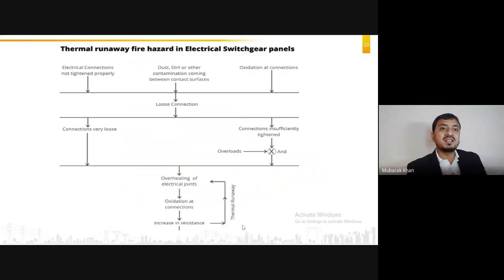I will try to explain the same thing from a broader perspective with the help of a flow chart. There can be three causes at the top: electrical connections not tightened properly, dust, dirt or contamination coming between the contact surfaces, or oxidation at the connection. Because of all these causes, there will be an effect known as a loose connection. Loose connections can be of two types: connections that are very loose, or connections that are insufficiently tightened.